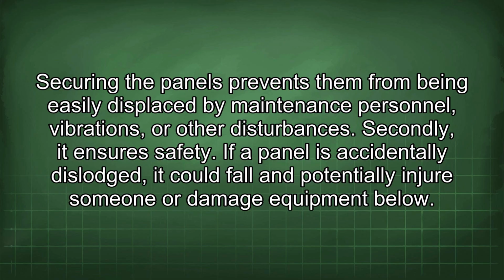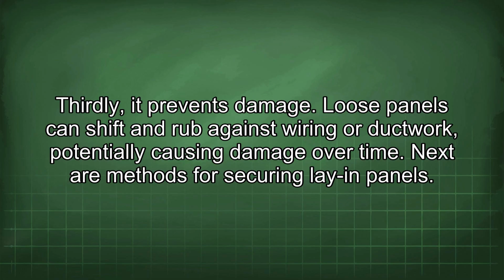Securing the panels prevents them from being easily displaced by maintenance personnel, vibrations, or other disturbances. Secondly, it ensures safety. If a panel is accidentally dislodged, it could fall and potentially injure someone or damage equipment below. Thirdly, it prevents damage. Loose panels can shift and rub against wiring or ductwork, potentially causing damage over time.